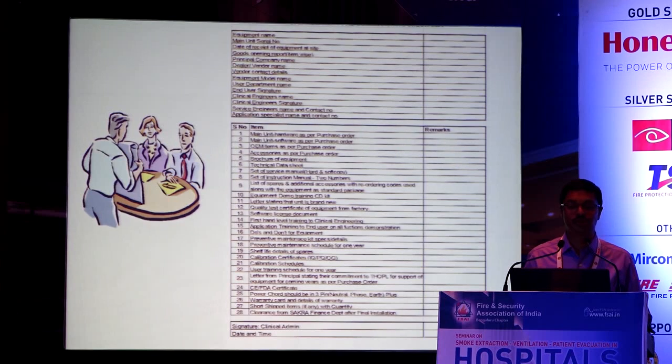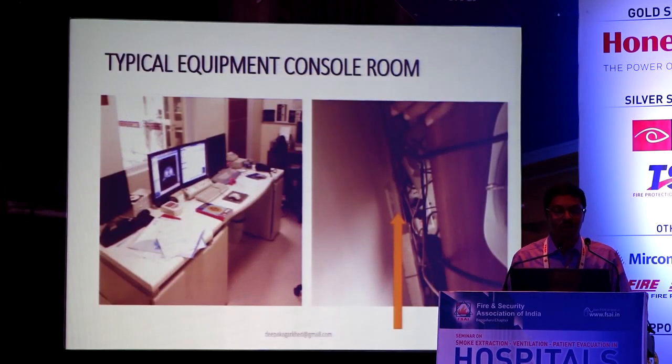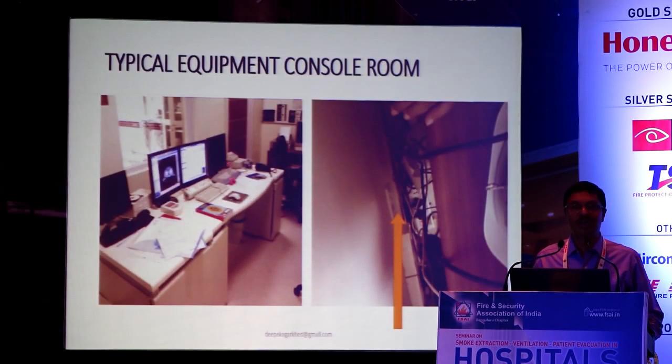This is a live example of one of the hospitals where I went for a survey. It's a console room. In a hospital scenario, most of you are from a hospital background, so I need not tell you: for major equipment, the technician sits in a console room and the patient is in the equipment room, or what we call a gantry room. You can see the console room looks okay, but if you look below, how many extension cords are there, how many cables are lying, there is no cable management.